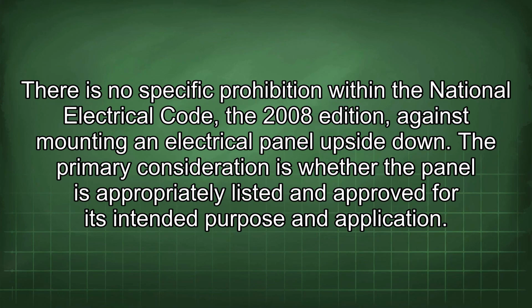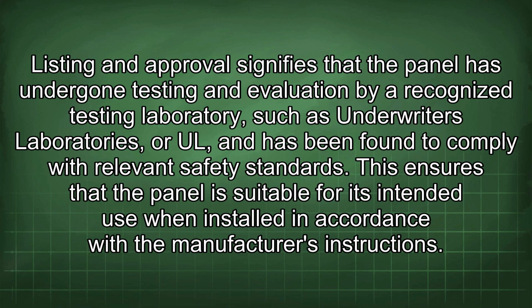There is no specific prohibition within the National Electrical Code, the 2008 edition, against mounting an electrical panel upside down. The primary consideration is whether the panel is appropriately listed and approved for its intended purpose and application. Listing and approval signifies that the panel has undergone testing and evaluation by a recognized testing laboratory such as Underwriters Laboratories, UL, and has been found to comply with relevant safety standards. This ensures that the panel is suitable for its intended use when installed in accordance with the manufacturer's instructions.